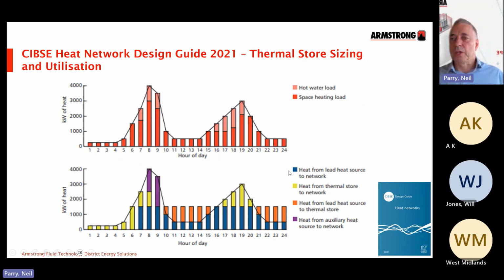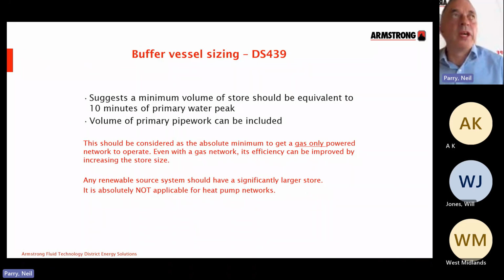So if we look at DS439, there's lots of information in there. DS439 being the Danish standard. There's lots of information on how to size that store, but the important aspect to mention here, this is sort of calculating the typical store size for a typical network. What it doesn't do is look at what your energy sources are, and I would advocate that the sizing methodology is not correct to use if you have, say, a heat pump only system or a largely heat pump led system. So we need to look at something else.